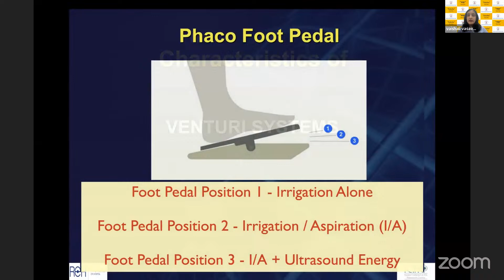But it is like a double-edged sword. I need to have extremely good control on my foot pedal and on my phaco tip movement because I am more likely to catch things. If I'm closer to an iris, because there is vacuum, there is suction, it will suck up the iris or a posterior capsule. So in Venturi, there is no separate flow rate and vacuum. You cannot separate the two. If you have a high vacuum, automatically more attraction. If you have a low vacuum, automatically low attraction. So it's just a one parameter system, which is in some cases faster and more efficient, but it needs exquisite control of your hand and your foot. So typically most of us are more comfortable with peristaltic machines.